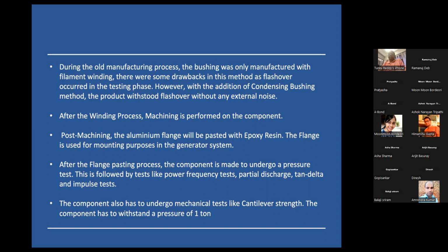Once the winding is finished, we can go for machining. Post machining, we have to apply another coating of epoxy resin on the aluminum flange. Now, why is the flange used? It's mainly used for mounting purposes in the generator system.